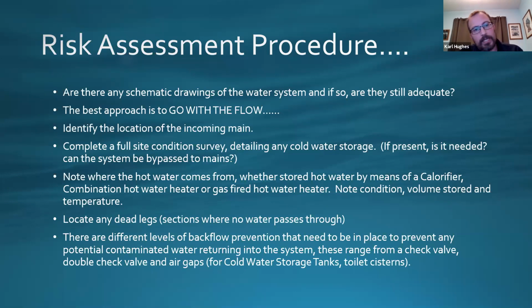What then can happen is, within there, you've got the stagnation, and any Legionella bacteria can then leach back into the system water. So you need to note those on the system diagrams and make a recommendation to get those removed. As I say, at the bottom there's obviously a lot more detail that you've got to go into.